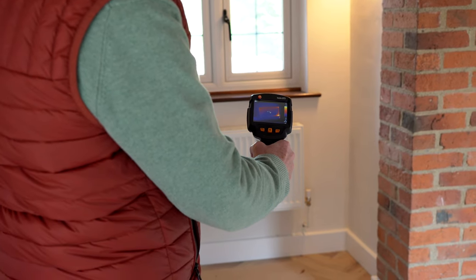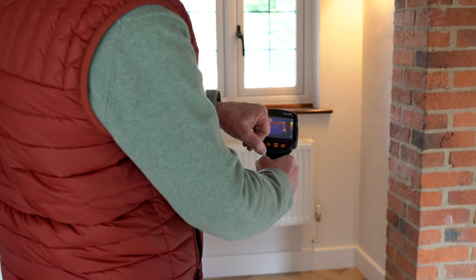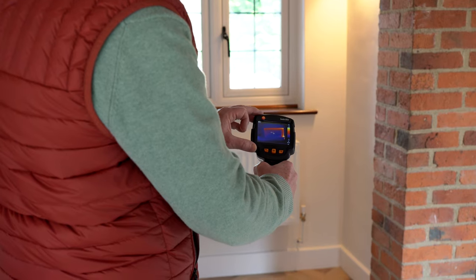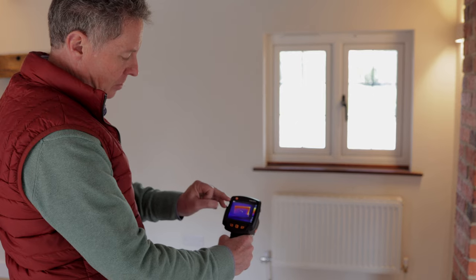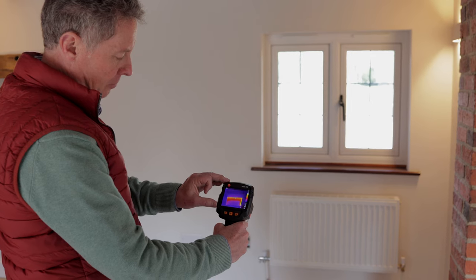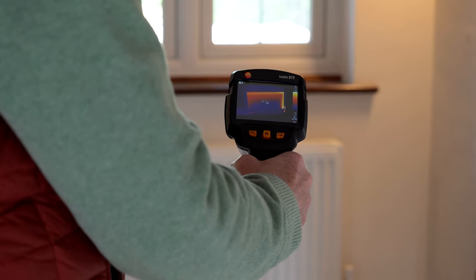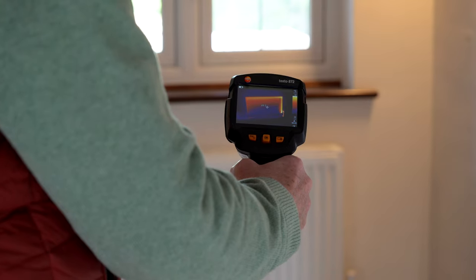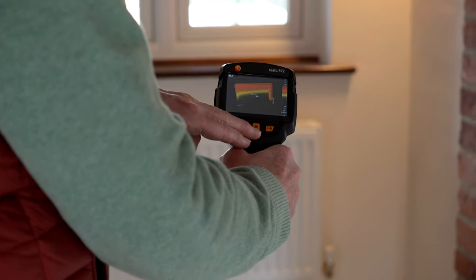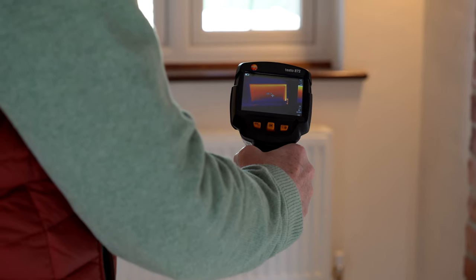Going back to the iron palette — this is interesting. We can actually see this radiator has been drained down or is starting to heat up, because all the temperature we saw just now has disappeared. We've just got a little bit of temperature coming into the radiator — it's actually warming up. We can see live now as the water is coming in from the hot upstand, going up and filling the radiator. The temperature from the top of the radiator is starting to come down — we're getting around 30 to 31 degrees at the top versus around 17.5 degrees elsewhere. You can clearly see the hot water coming in, going through and filling the radiator, giving a much more even temperature across it. If a radiator was blocked at the bottom, you'd have a permanently cold area of sludge, and that will be very, very clear and very visual with the camera.